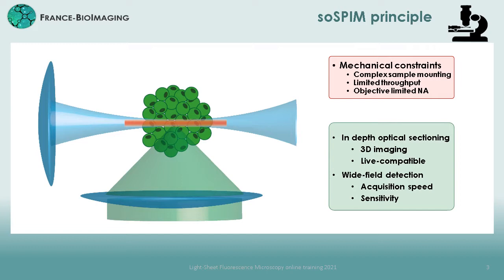However, this multi-objective architecture comes with important mechanical constraints. On one side, it complexifies the way to mount samples in between the objectives and thus limits the potential imaging throughput. On the other side, it prevents the possibility to use high numerical aperture objectives, which are usually bulkier, and hence limits the resolution and the overall sensitivity of the system.